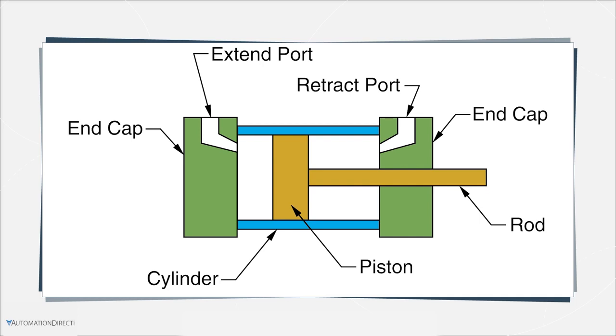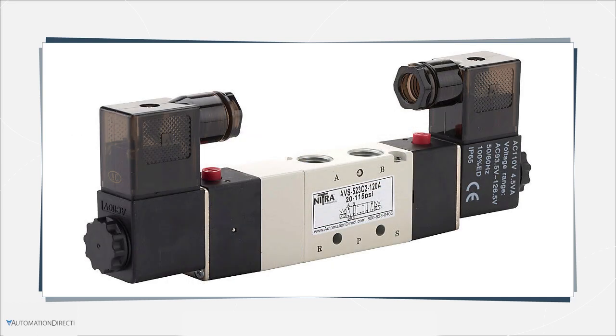In a typical application, the actuator body is connected to a support frame and the end of the rod is connected to a machine element that is to be moved. A directional control valve is used to provide a path of compressed air to the extend port, while allowing the exhaust air to escape through the valve to the atmosphere.